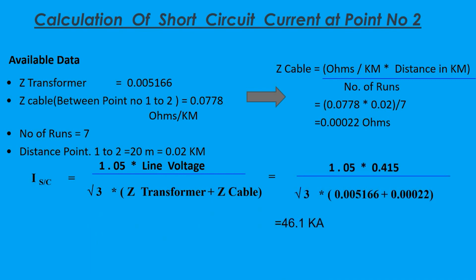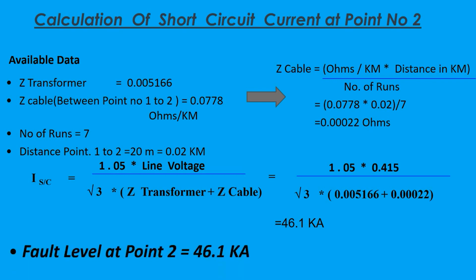ISC equals 1.05 times the line voltage, all divided by root 3 times Z transformer plus Z cable, that equals 1.05 times 0.415, all divided by root 3 times 0.005166 plus 0.00022, which equals 46.1 kilo amperes. So the fault level at point number two is 46.1 kilo amperes.